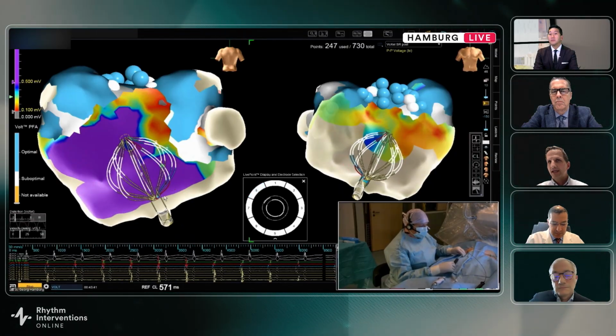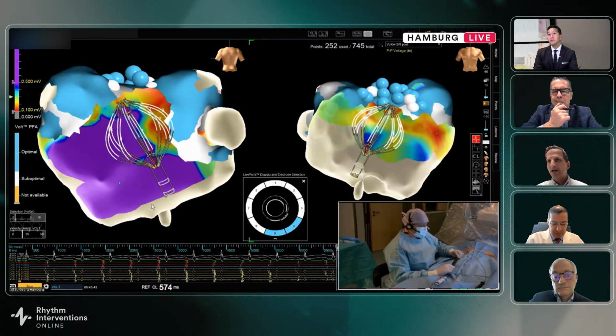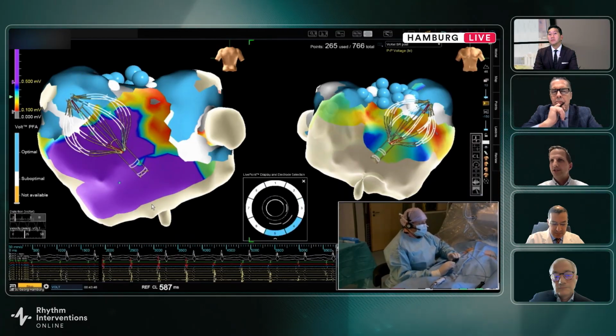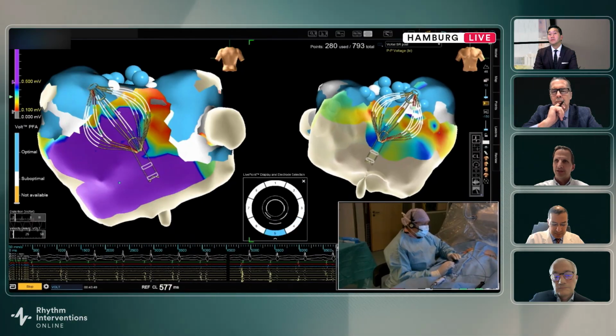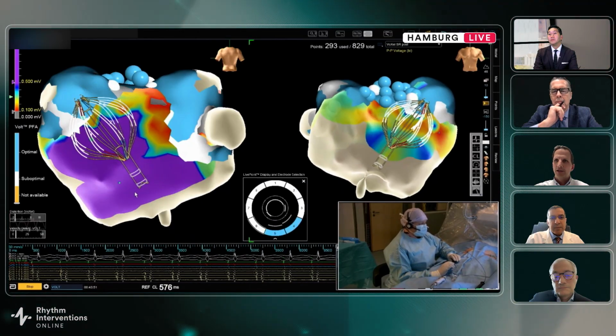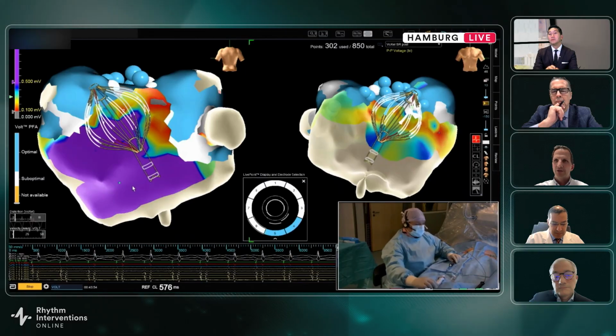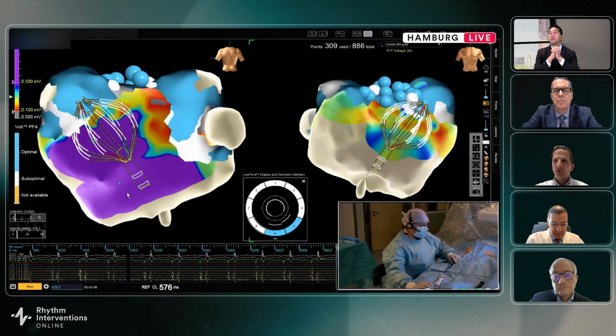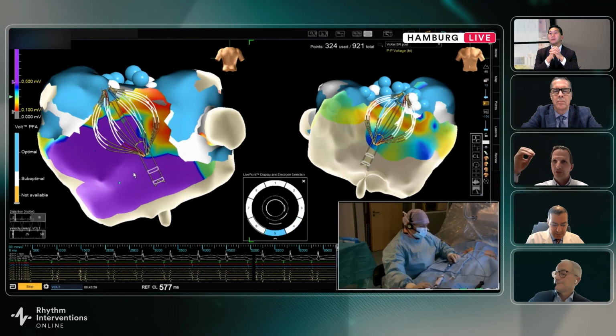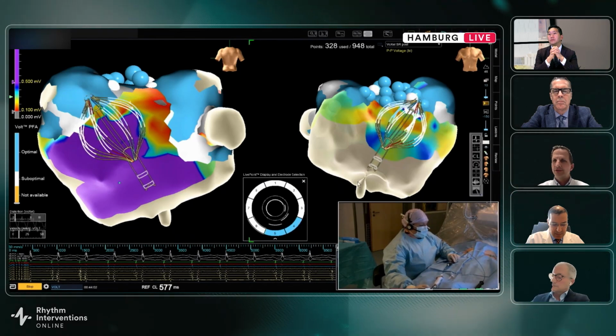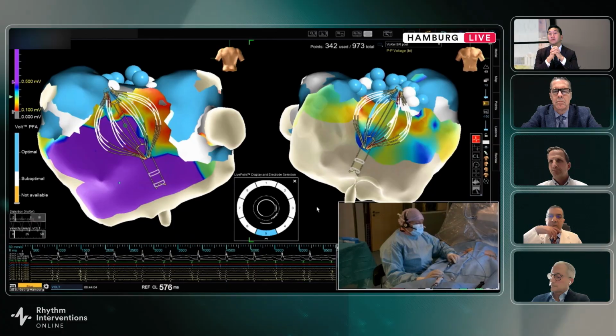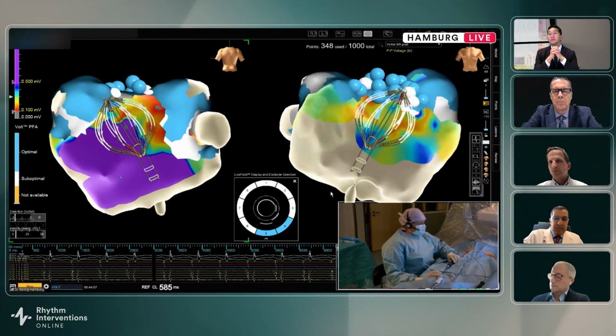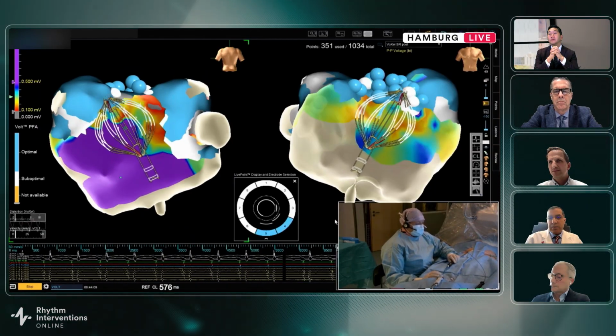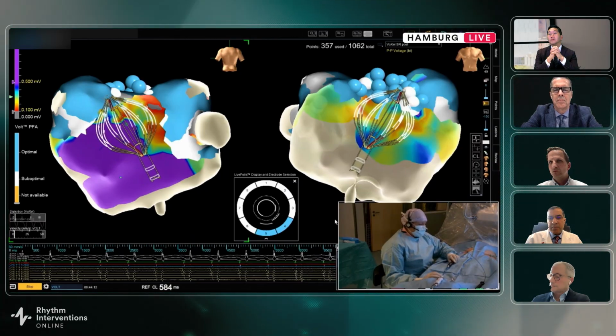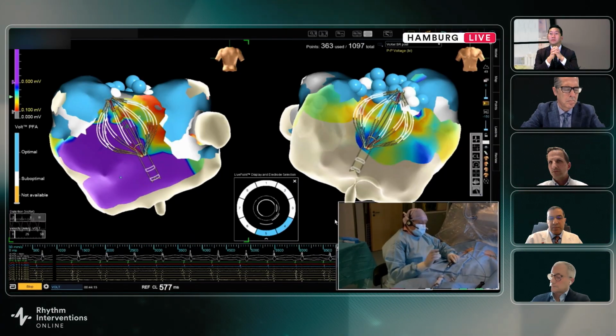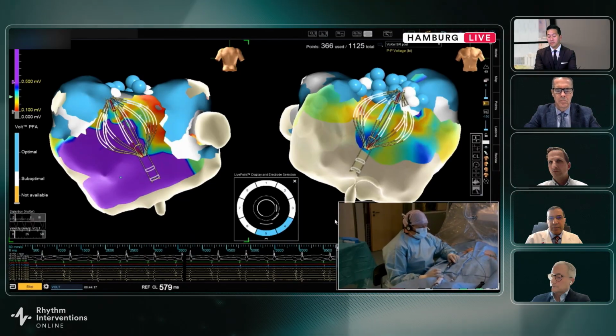Exactly. And per design, you're allowed to use it with wire or without wire. The only thing you must not do is keep the wire 0.5 centimeter out, because then it's like a knife. So we would typically use it in most situations with the wire outside, but there are some situations for the posterior wall where we keep the wire inside. What about you, Ari? Do you always keep the wire out, or do you sometimes keep it? Yeah, I mean, the more we learn, the braver we might get. For the posterior wall, if we have a large left atrium, you have enough space, then we might even not keep the wire out. As you said, you should keep it short, because then it can be really dangerous.